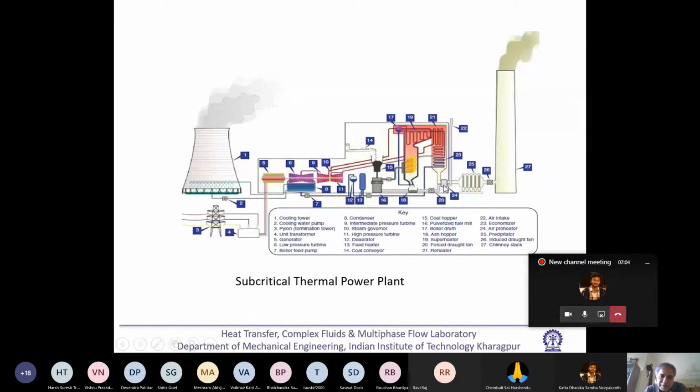Even here there is one heat exchanger, which is your air preheater. So as the gas moves in this direction, its temperature reduces. So at the lowest temperature, we have got the air preheater. Then we have got the economizer, where the water is being heated, then the reheater, and then different superheaters. So this is what. And at the wall of the boiler, we have got the tubes embedded. So these are called water tubes, and obviously a good amount of heat is also being absorbed by that.